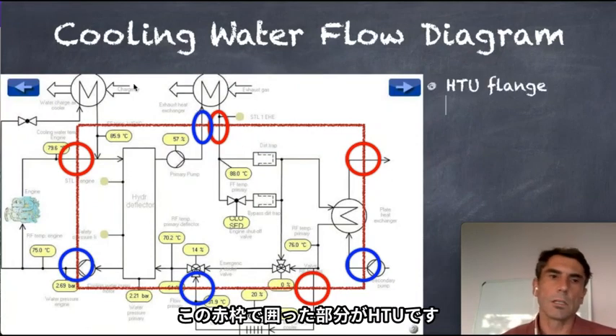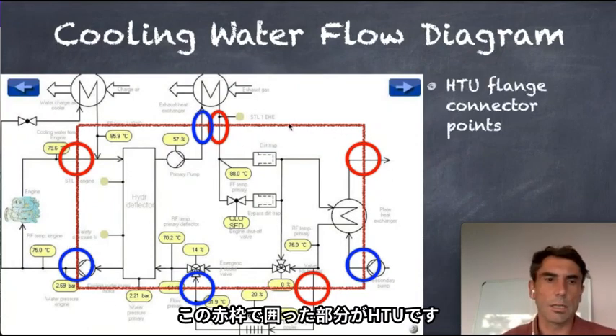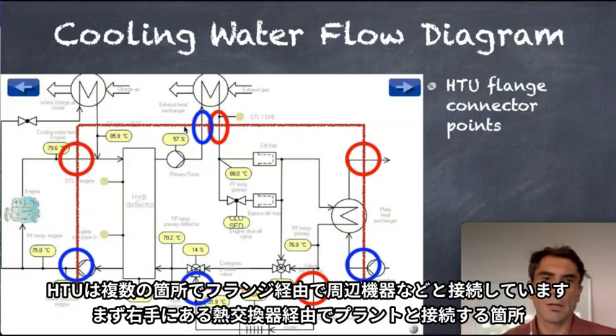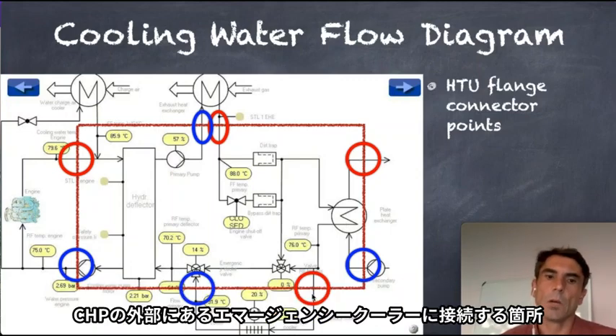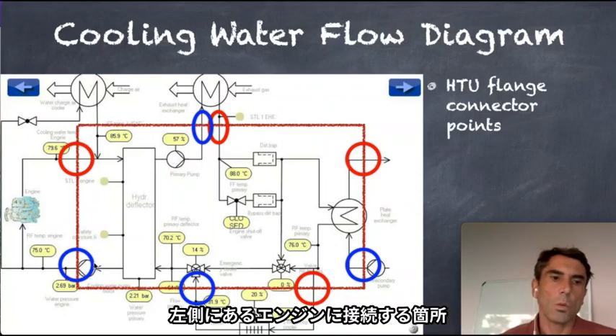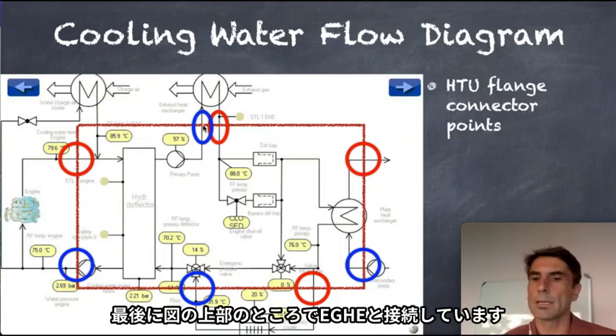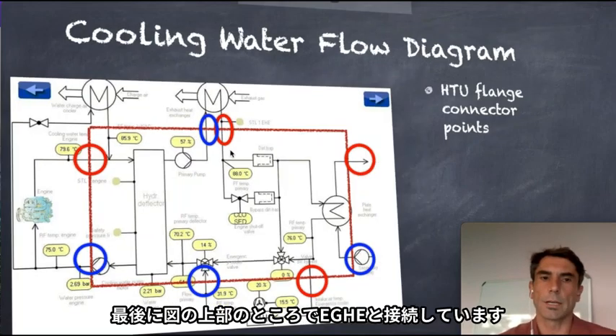So we have here the cooling water flow of the HTU. That's the HTU actually. So we have flange connectors on the HTU. One thing is the supply to the client or to the plant at the plate heat exchanger. We have connector for the external emergency cooler cycle. We have connectors for the engine, where the engine cycle is connected. And we have connectors at the exhaust gas heat exchanger, where the external exhaust gas heat exchanger is connected.